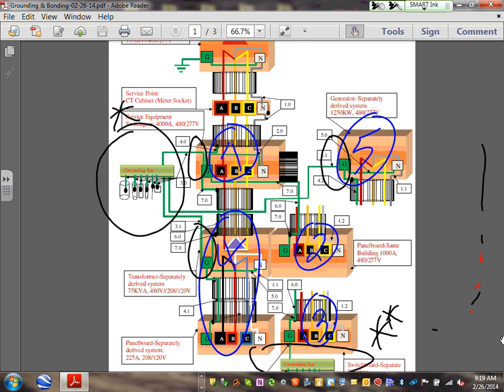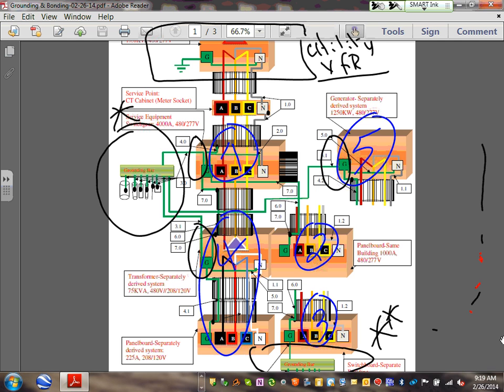This transformer, guys, you shall not be responsible for that one. This is the utility transformer. We don't mess with it. They ground it themselves, so we don't mess with that transformer, right? It sits there. We provide a conduit so they can put their wires coming to our termination box. So that's why I didn't talk about that one. It's already grounded. They bring it grounded on the 480, but we don't mess with it.